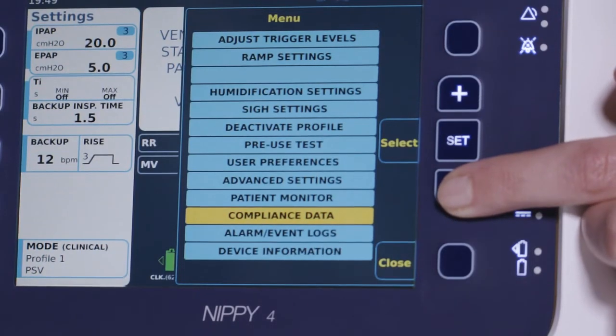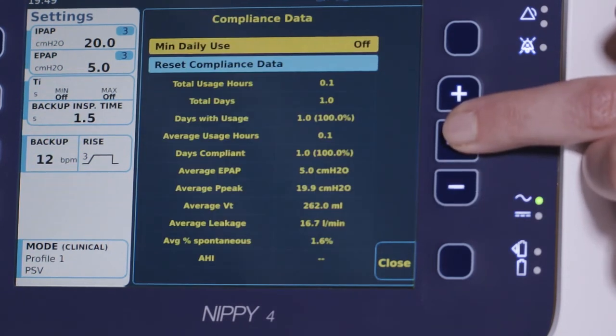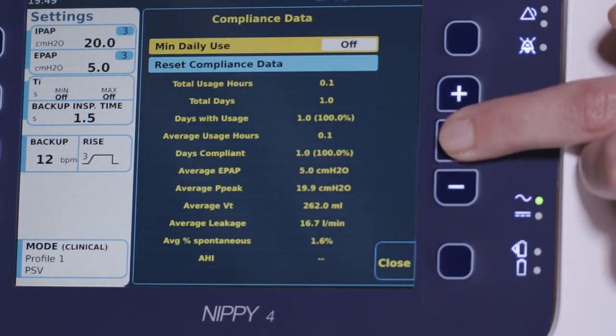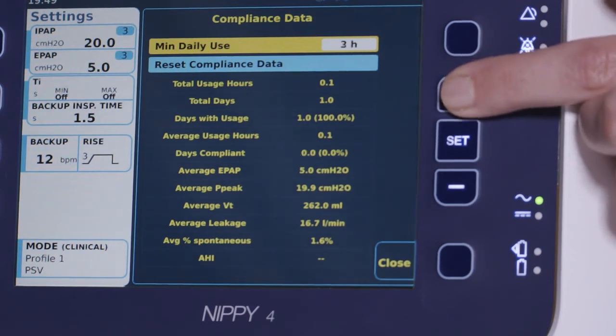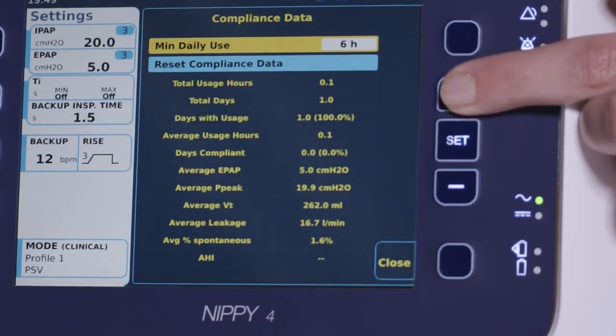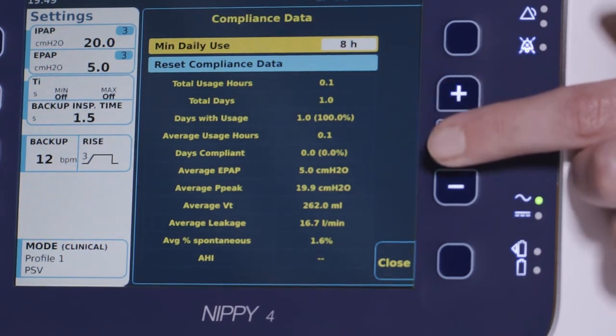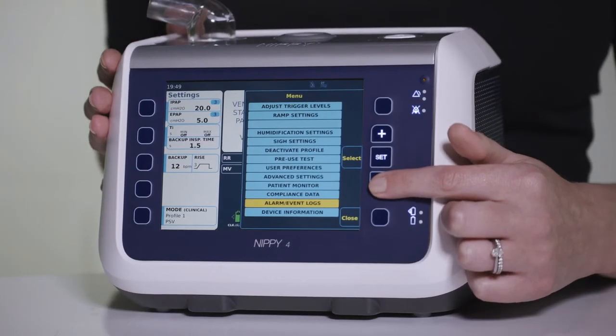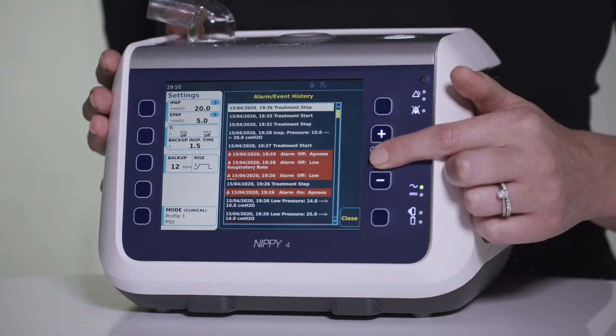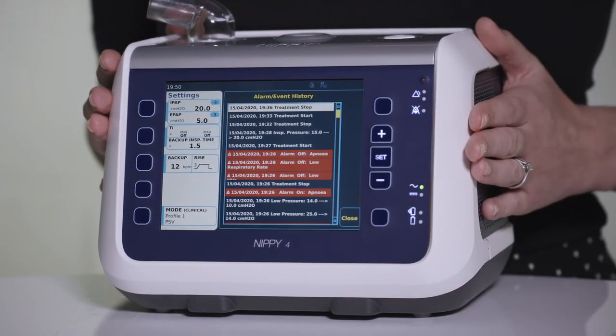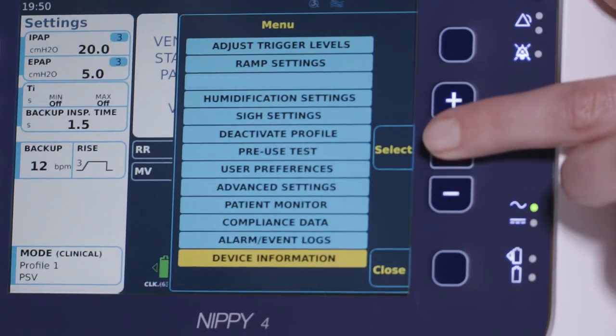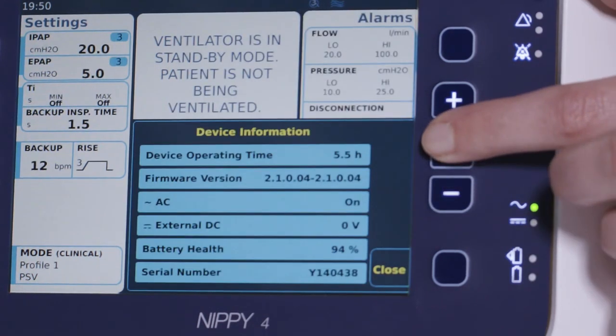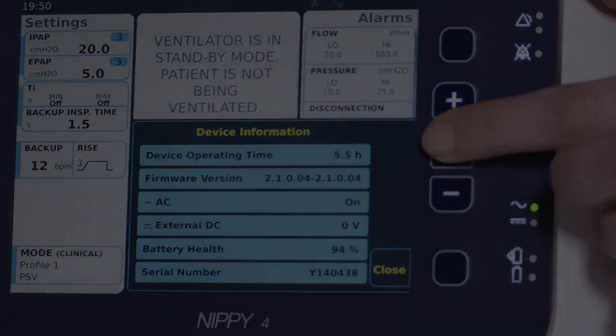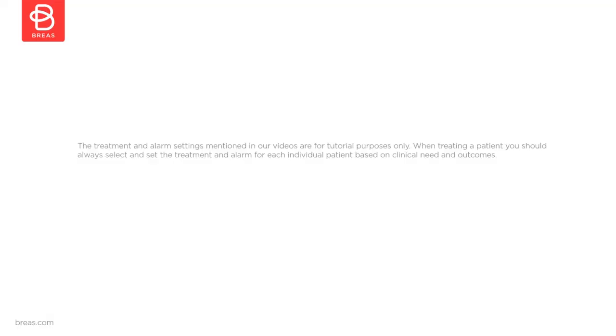The remainder of the main menu consists of the patient's summary compliance data, in which you can set a preferred level of daily use to measure this data against. The alarm event log. Some device information where you will find the firmware version in use, the percentage health of the internal battery, and the device's serial number.